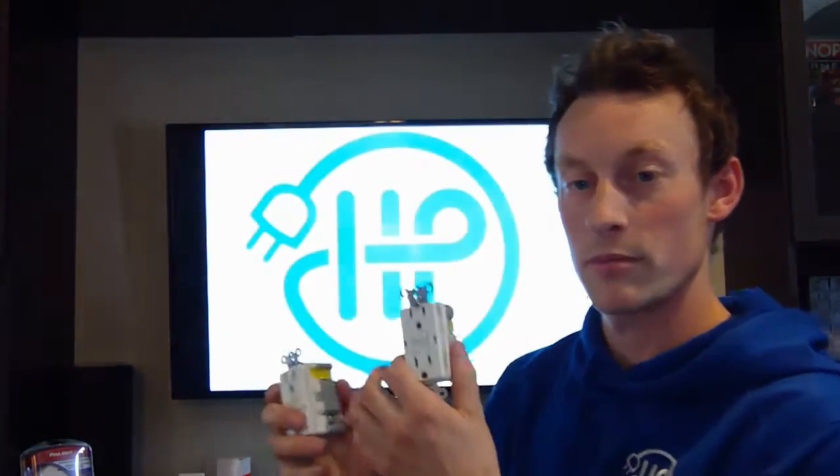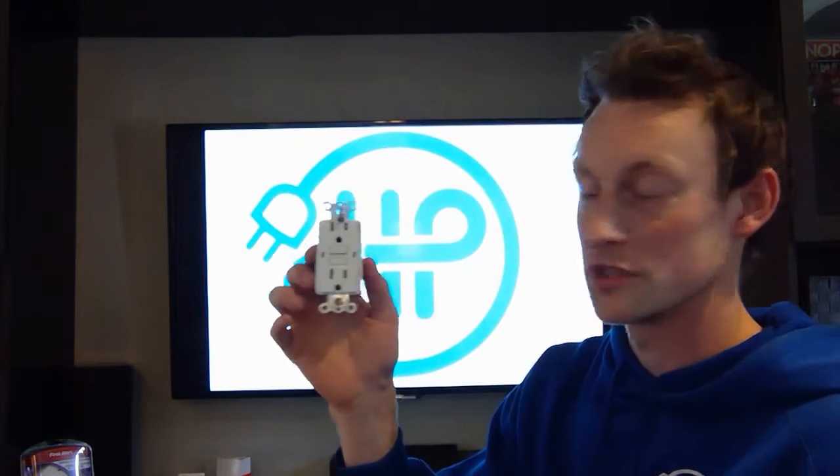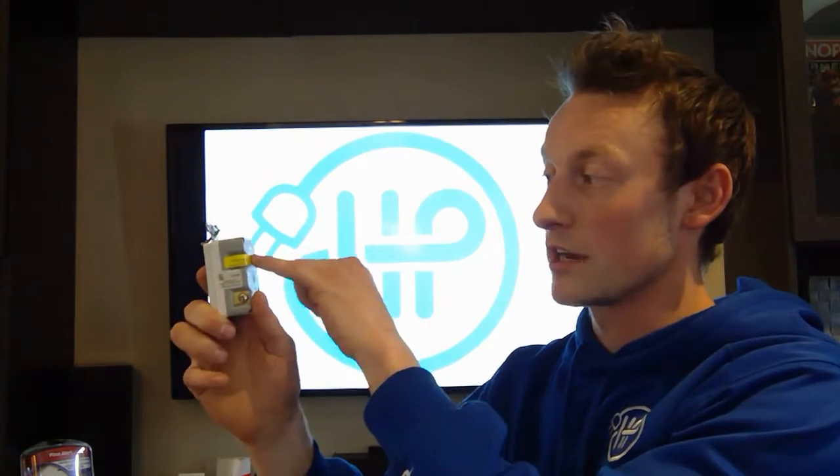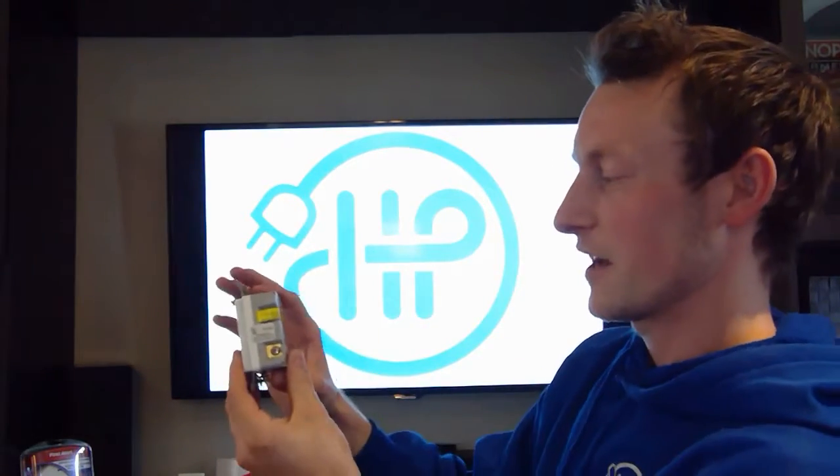Say you have your power from your panel coming first to a GFI receptacle right here. This is in your master bathroom upstairs, or any other bathroom. You're going to have your power coming in from your breaker at your panel, regular breaker, into your line side. Now, if you don't want to have to spend the cost of another GFI receptacle in your other bathroom, or maybe you share it with an outside plug, then what you're going to do is come out of your load side and go to all the other plugs that you want to protect.